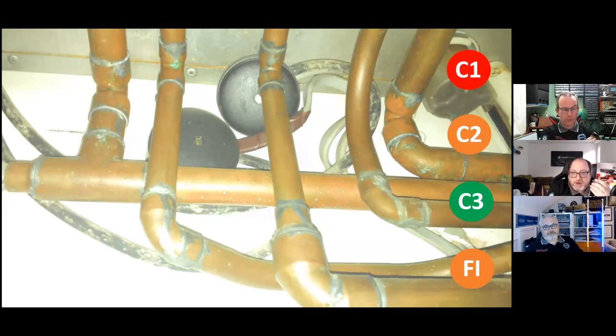Doesn't mean I change my code, but I will always make sure I've done a huge amount of investigation work to make sure there is no potential danger in that scenario. It's very important. Just mentioning the Emma Shore stuff, you are right. The risk of having electrical connections floating near conductive pipework, if there was a failure, even of that crappy insulating tape on a single sheath conductor, because obviously it's damaged, you could say that is potentially dangerous, urgent remedial action required. But this is me doing a drive-by now.